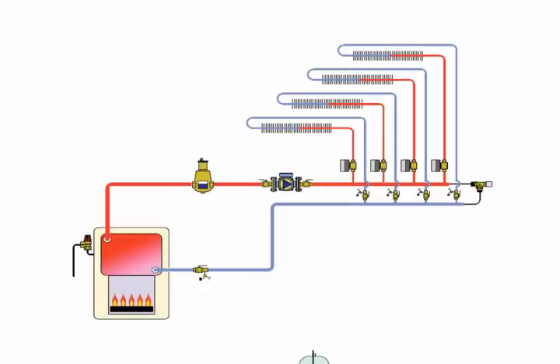Now speaking of pressures, what is the pressure in the system when that pump fires on? We don't know because we don't have an expansion tank on here, right? The expansion tank is always your reference point. It has a compressible diaphragm in it, if it's that type of expansion tank. As that pump fires on and off, or even multiple pumps firing on and off, the pressure at which that expansion tank joins the system, the pressure it started with before the pumps were on, never changes. It's the point of no pressure change in your system. So why is that an issue?